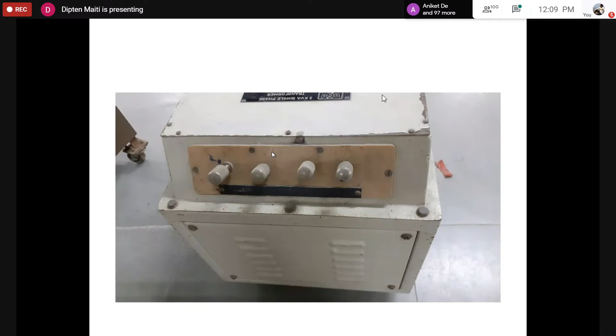How can we check that? We would check that by measuring the resistance between any two possible terminals, and if I find that resistance is low, low usually means very low, though that depends. For a very low rating transformer with small VA rating, that can be of the order of tens of ohms of resistance. However, for a larger transformer, that can be of the order of even milliohms of resistance.